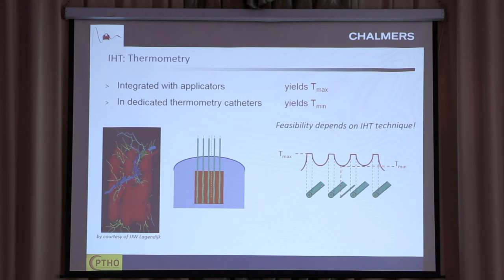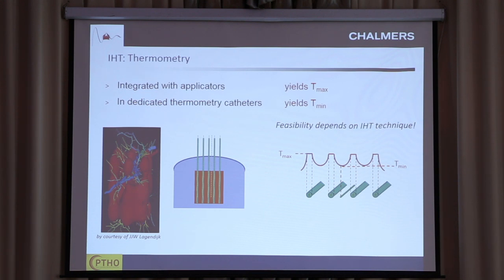And then you have your catheters, and you have to select which ones you will use for heating and which ones you will use for thermometry. That could be tricky. There are two thermometry techniques: you can have thermometry integrated with the applicators, or dedicated thermometric catheters. One should be aware that the temperature measurement will be very different. If you have the thermometry in your catheter close to your implant, you will measure the maximum temperature, because around it is the maximum field. On the other hand, if your thermometer is in between, you will rather measure the minimum temperature. So you should be aware of this when reporting and analyzing the data.